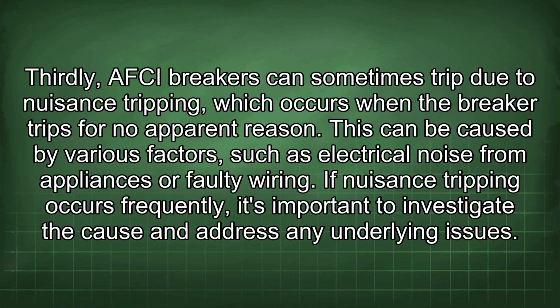Thirdly, AFCI breakers can sometimes trip due to nuisance tripping, which occurs when the breaker trips for no apparent reason. This can be caused by various factors, such as electrical noise from appliances or faulty wiring. If nuisance tripping occurs frequently, it's important to investigate the cause and address any underlying issues.